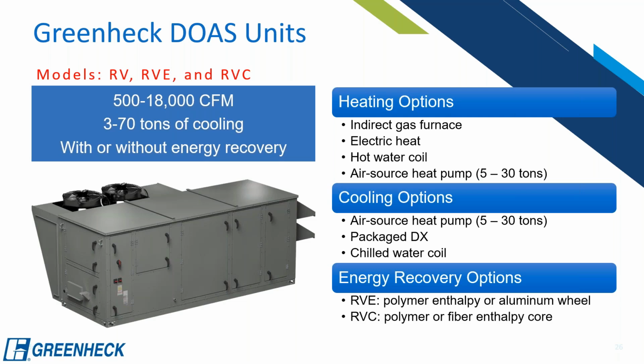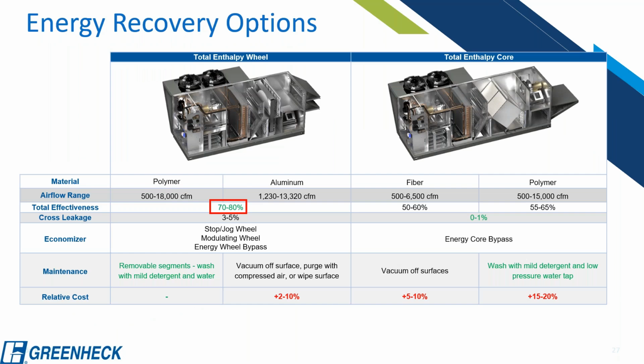Now, the two big differences in our RVE and RVC is that the RVE has a polymer enthalpy wheel or aluminum wheel, and the RVC has a polymer or fiber enthalpy core. And for our market, I really want to push you towards the enthalpy wheel. There's some concerns there with it being high maintenance or cross leakage, but I want to really put a stop to that because one, cross leakage is well below what you need for even a class 3 exhaust space. And then two, we have a really great relationship with Air Exchange right down the street in Hanover. And if anything ever were to happen to a wheel, which they don't for the most part, we could handle that immediately. But that said, we can get a total effectiveness of 70 to 80% with the wheel, the total enthalpy wheel RVE model. And by the way, the polymer version of this is actually the most economical in terms of relative cost.